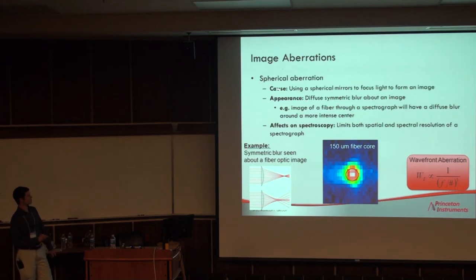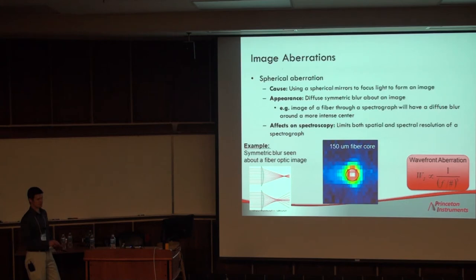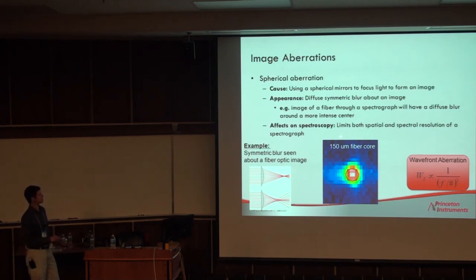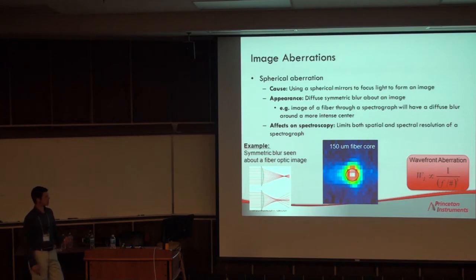Spherical aberration, shown here through a ray trace, is caused by the use of a spherical mirror or lens to form an image. It appears as a radial blur about the imaged object — in this case a 150-micron core fiber gets blurred out to a 180 to 200-micron image. Its effects on spectroscopy limit both spatial and spectral resolution in the instrument. It also goes as one over the F-number cubed, so the shorter the focal length, this effect increases rapidly.